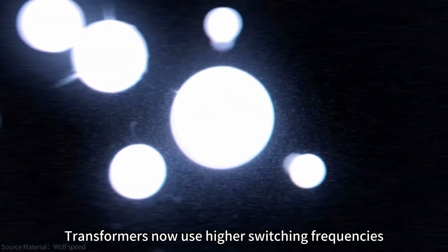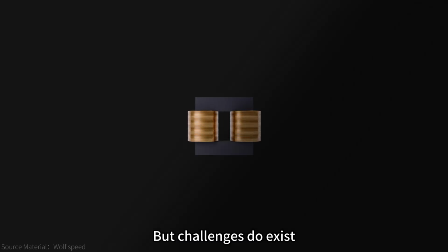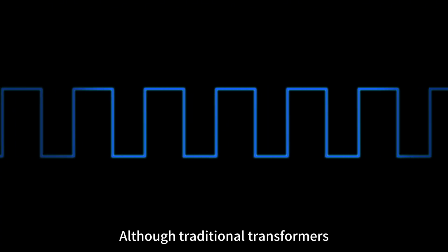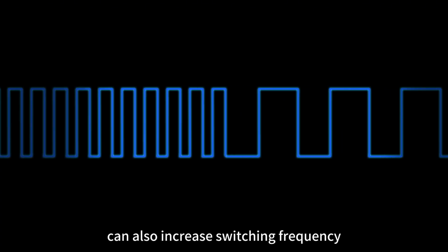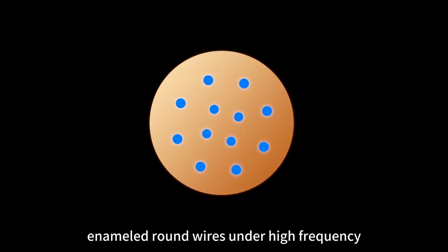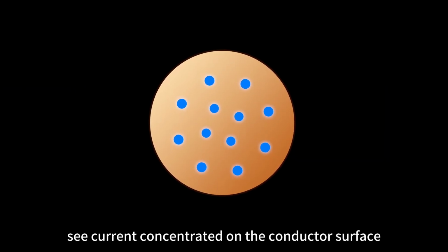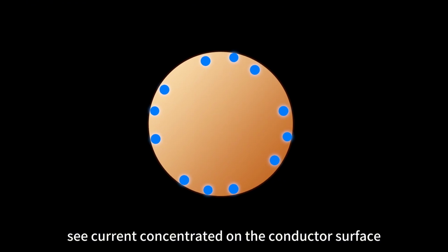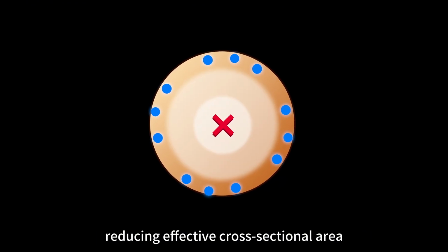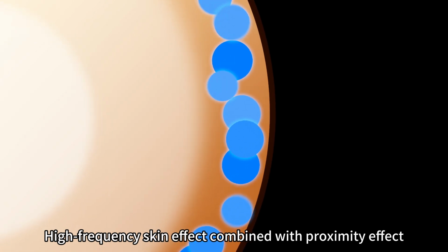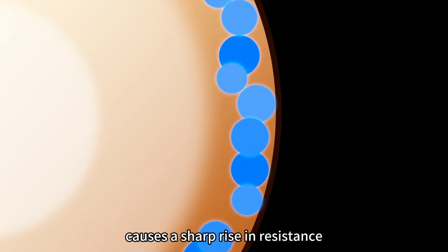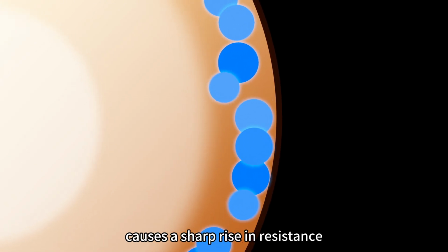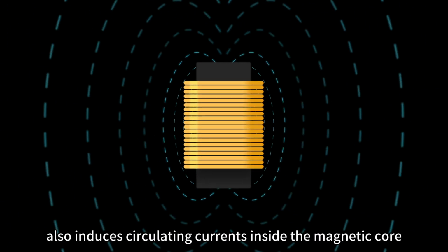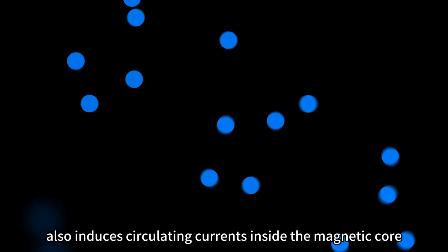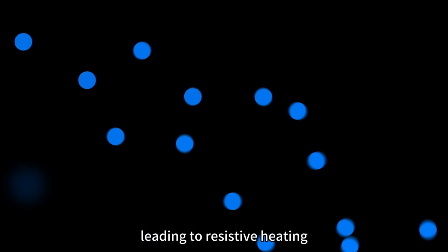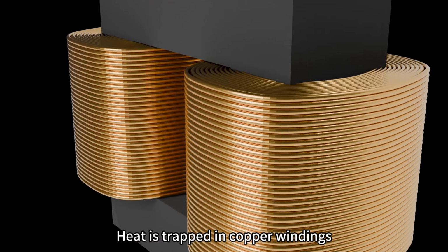Third-generation semiconductors are spreading, and transformers now use higher switching frequencies, but challenges exist. Although traditional transformers can also increase switching frequency, enameled round wires under high frequency see current concentrated on the conductor surface, reducing effective cross-sectional area. High-frequency skin effect combined with proximity effect causes a sharp rise in resistance. A changing magnetic field also induces circulating currents inside the magnetic core, leading to resistive heating. Heat is trapped in copper windings, and dissipation is difficult.